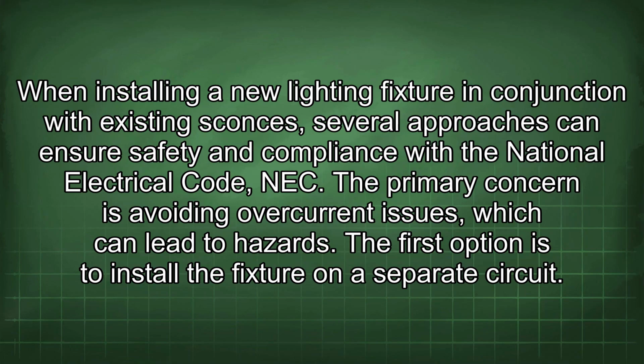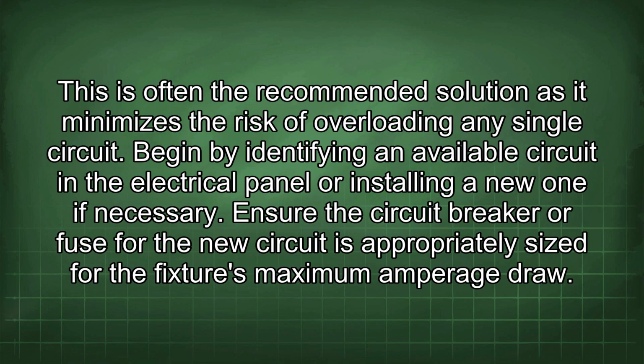When installing a new lighting fixture in conjunction with existing sconces, several approaches can ensure safety and compliance with the National Electrical Code (NEC). The primary concern is avoiding overcurrent issues, which can lead to hazards. The first option is to install the fixture on a separate circuit. This is often the recommended solution as it minimizes the risk of overloading any single circuit.